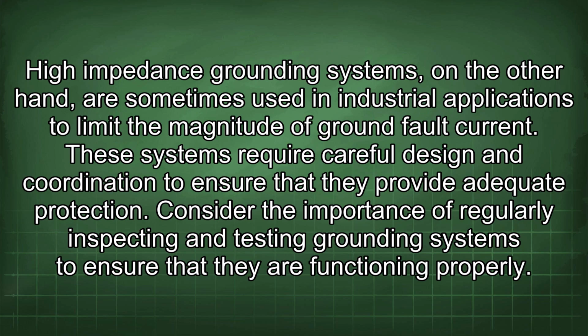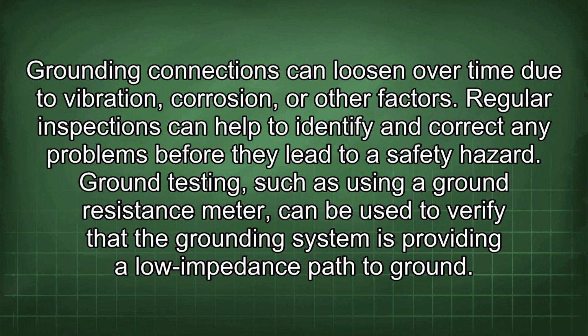Consider the importance of regularly inspecting and testing grounding systems to ensure that they are functioning properly. Grounding connections can loosen over time due to vibration, corrosion, or other factors. Regular inspections can help to identify and correct any problems before they lead to a safety hazard. Ground testing, such as using a ground resistance meter, can be used to verify that the grounding system is providing a low impedance path to ground.